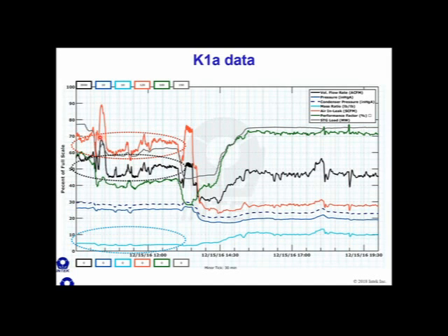So here's the data when we arrived. Again, red is air in leakage. This is a different plot. This is a percent scale over here, and the maximum value for each line is shown up here. So 100% is 120 SCFM up here. So 60% of 120 is about 70 SCFM, 80 SCFM right here.